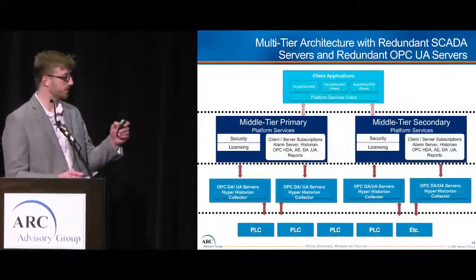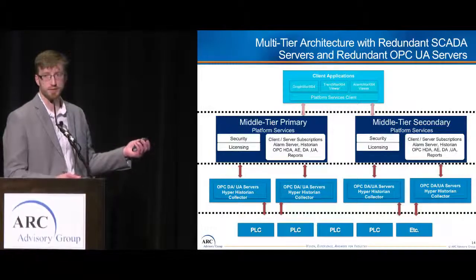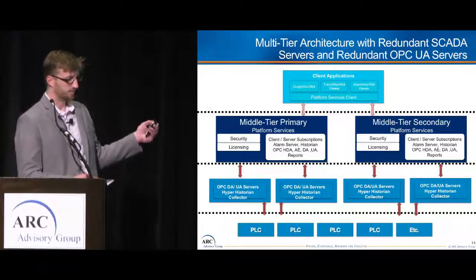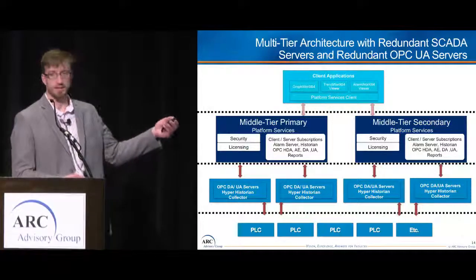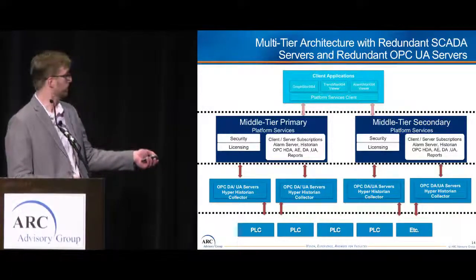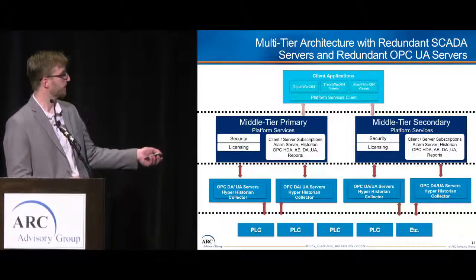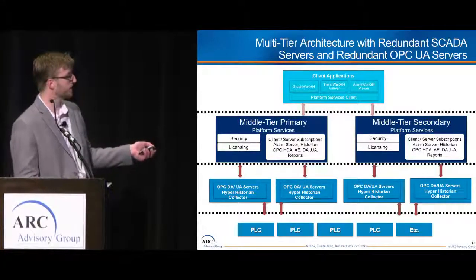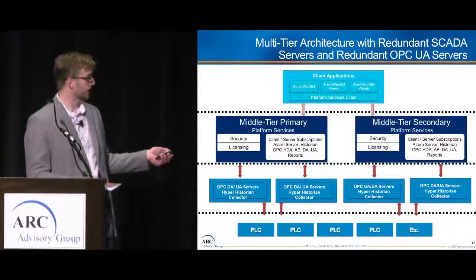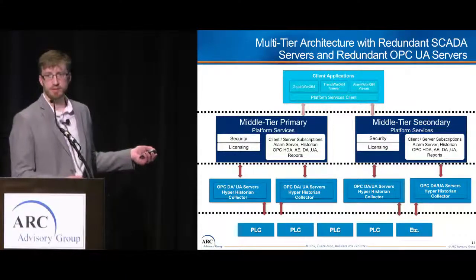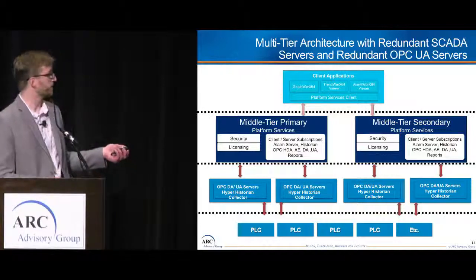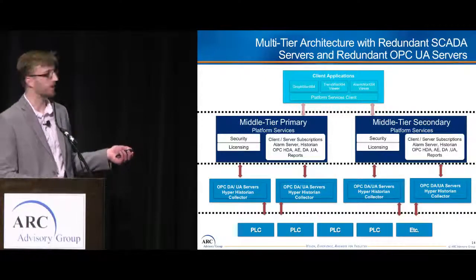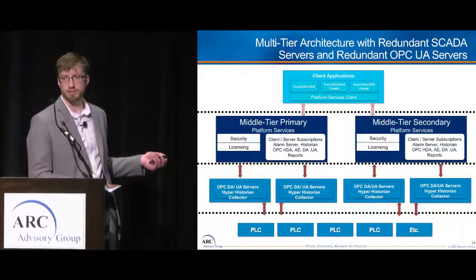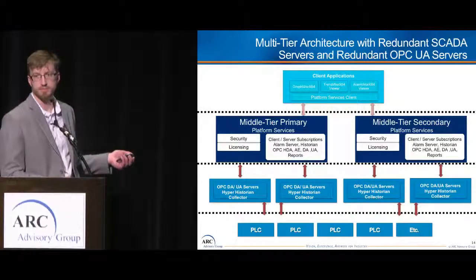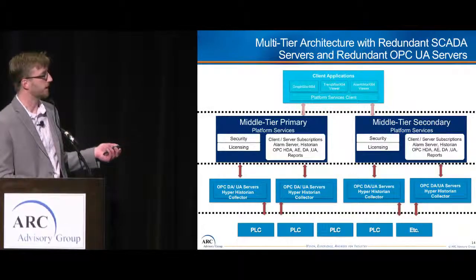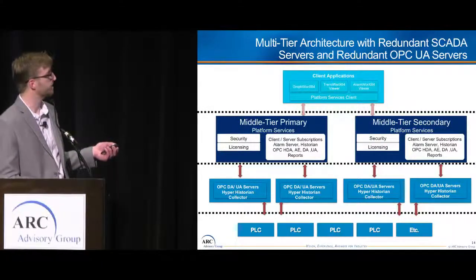So this is just a generic drawing of our architecture, and it's definitely scaled from this. Down here you have your control network - we have redundant OPC DA and UA servers. We put our historian collectors on those same machines because we wanted that data collection to happen as close to the data source as possible. Those historian data collectors can store and forward data up to our hyperhistorians and SCADA system.